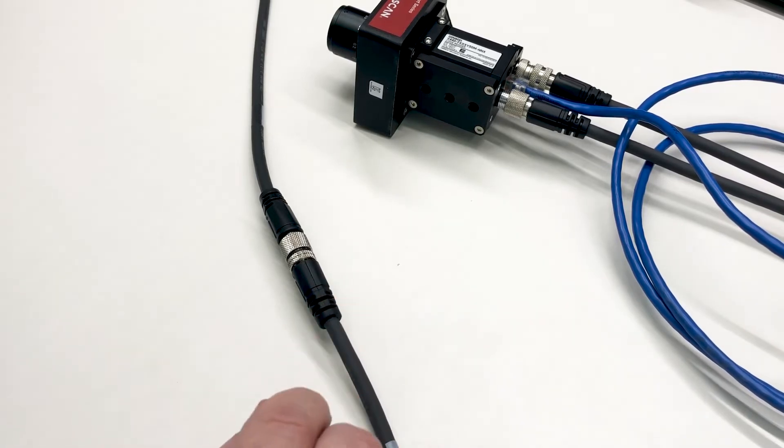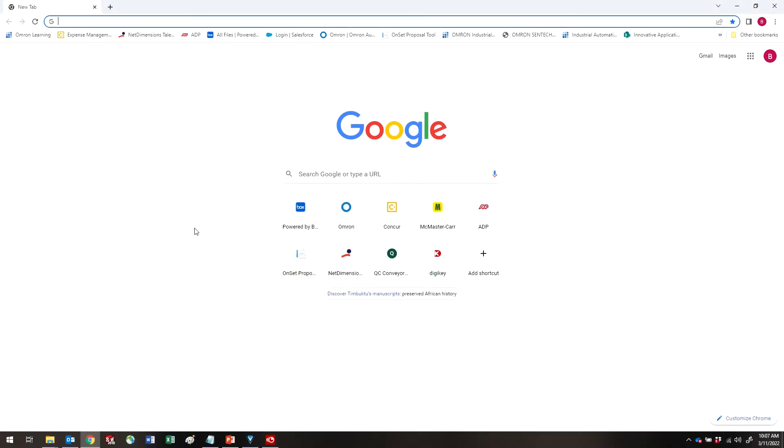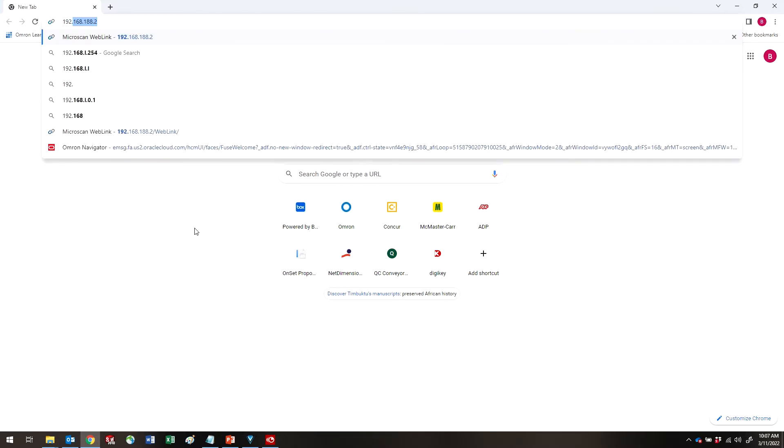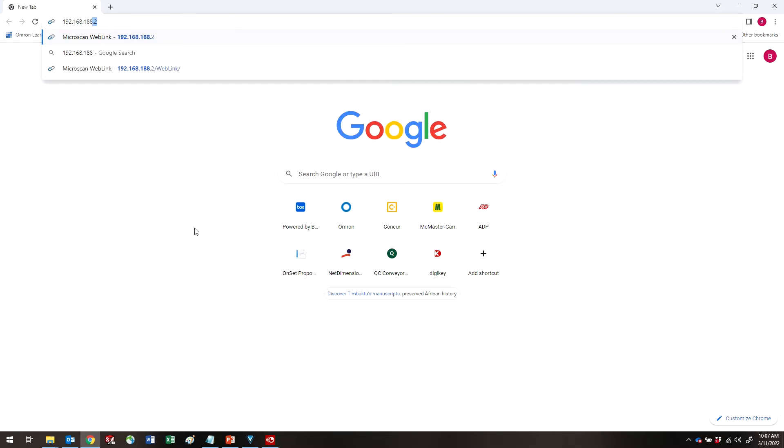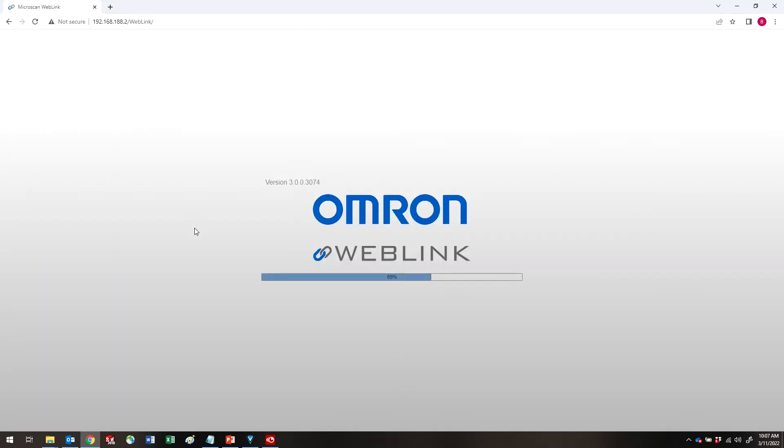You can now mount your V440 to your equipment. Once you have the V440 powered and connected to your computer, you can start your web browser. In your web browser, enter the V440's address. The default address is 192.168.188.2. OMRON WEBLINK will automatically start.